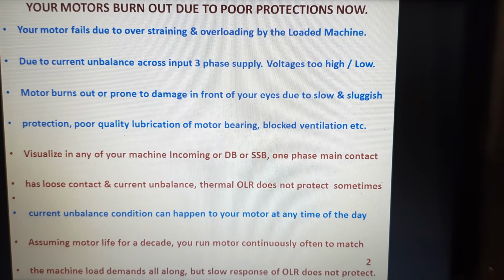So, visualize in any of your machine incoming or the DB or the SSB, one main phase contact has gone loose and current unbalance happens, and the thermal OLR does not protect at some times of the day. The current unbalance condition can happen to the motor at any time of the day. Assuming the motor life is a decade, you run your motor continuously, often to match the machine loads all along, but the slow response of the OLR does not protect.